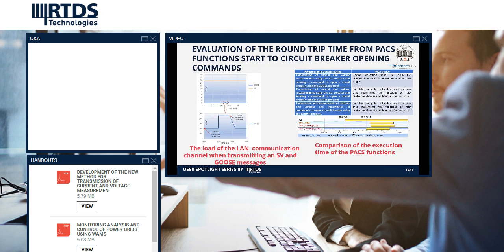For the substation as a whole, the process bus load can be reduced by 1,000 to 3,000 times, depending on the substation scheme and the number of bays. Compared to SV streams, in normal condition, it reduces the load of the process bus by more than 2,000 times, depending on the scheme of the substation and number of bays, while maintaining the required speed of the algorithm.